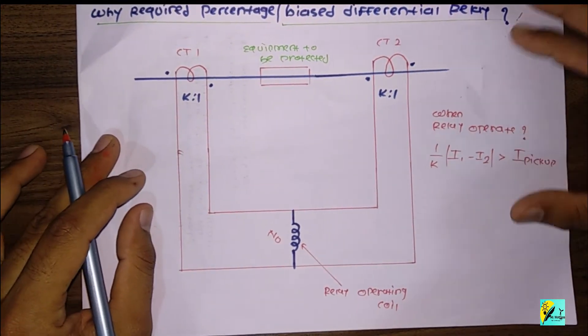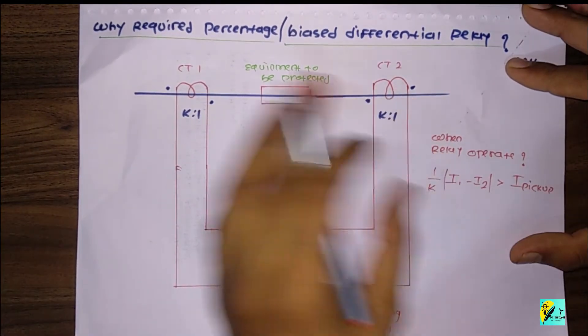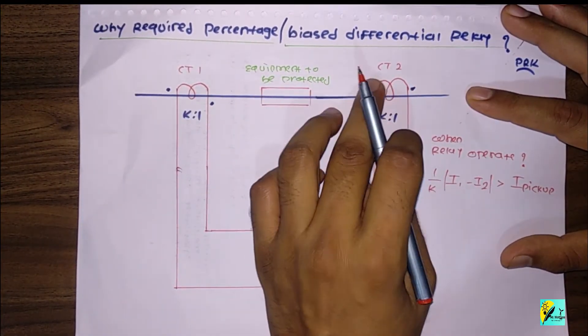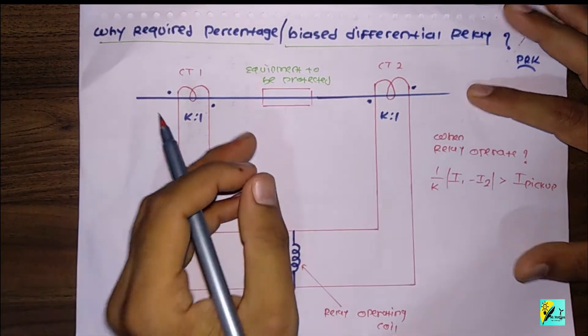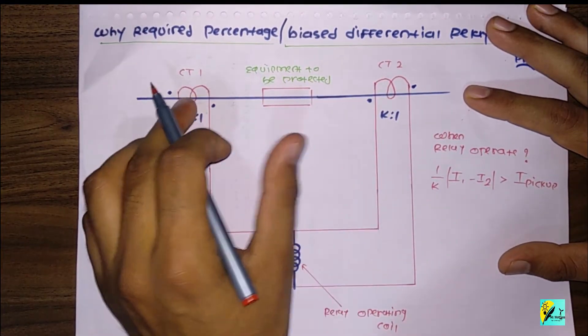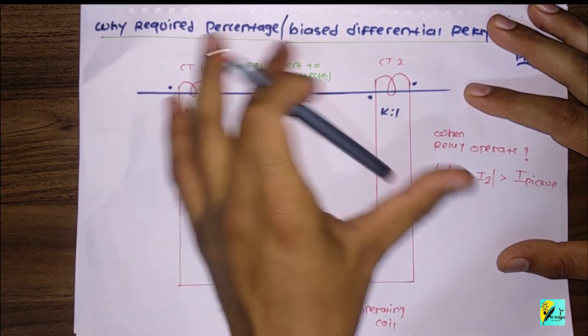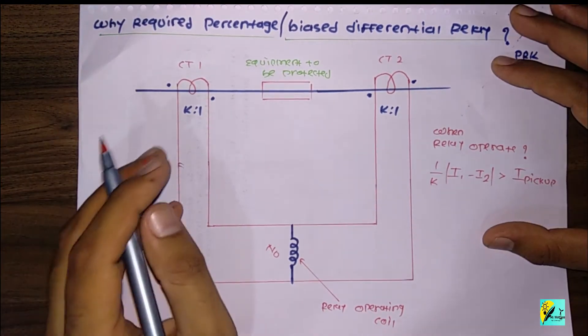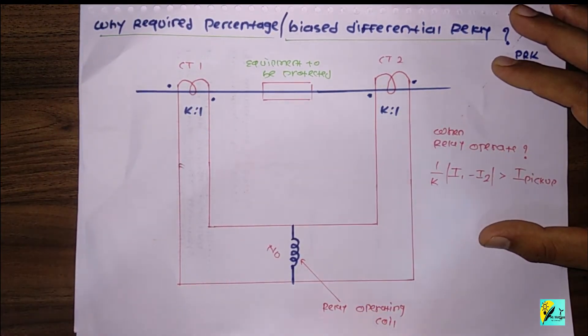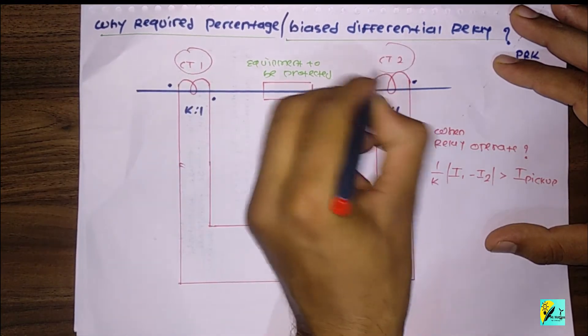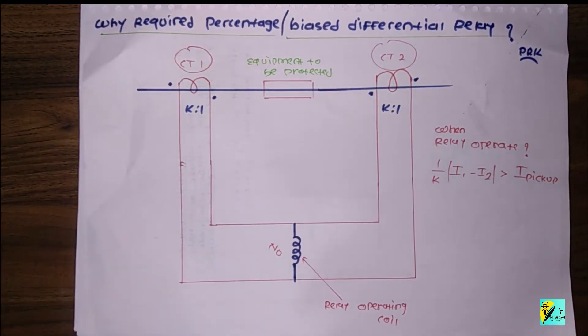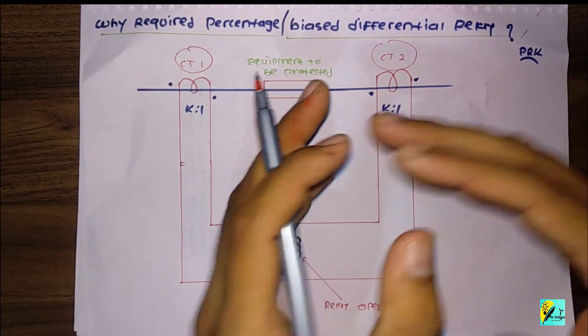We have already seen the differential relay and the working of CT1 and CT2. In this particular section between CT1 and CT2 is the equipment to be protected. One factor that should be considered is that the ratio of CT1 and CT2 should be identical in nature. If these two transformation ratios are not equal, then the secondary currents will not be equal.